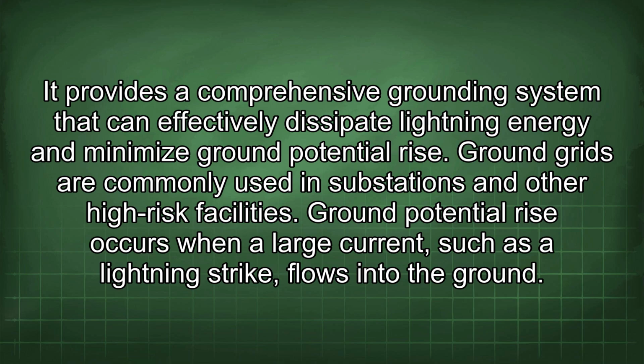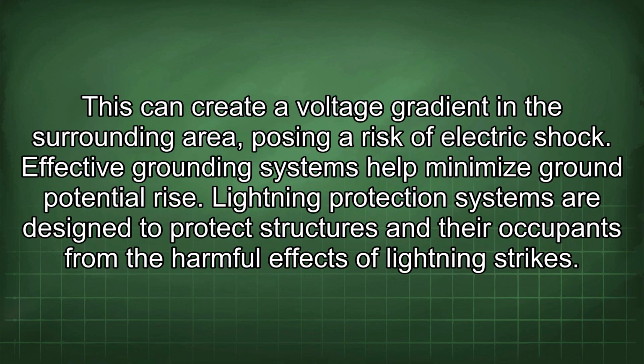Ground potential rise occurs when a large current, such as a lightning strike, flows into the ground. This can create a voltage gradient in the surrounding area, posing a risk of electric shock. Effective grounding systems help minimize ground potential rise.